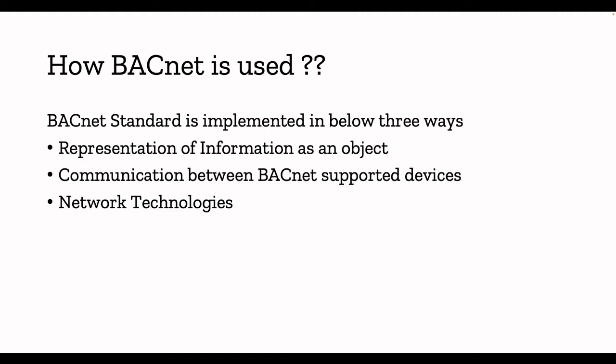Basically, if you want to use BACnet, the BACnet standard is implemented in three ways. First is the representation of information as an object. In BACnet, all the information and data stored inside a BACnet device is defined as an object — just like object-oriented programming, where we define everything as an individual object. Each object has a different set of properties. For example, if I want to access a temperature sensor, it could be an analog input object.